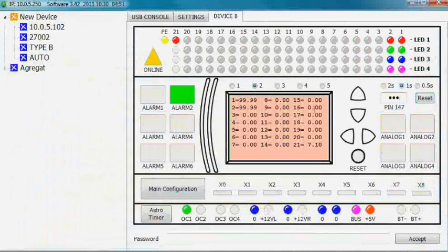Notice that the resistance value has changed. This is because we connected another resistor that imitates a sensor in line with the previous resistor. Now, when the zone is armed, change the resistance by connecting a resistor to the input in a parallel way. As you can see, the input reacted to the change in resistance and triggered the alarm.